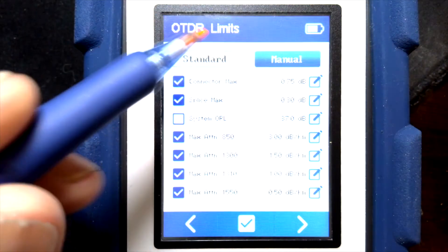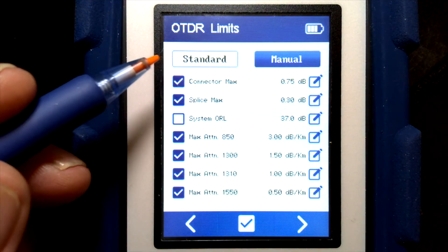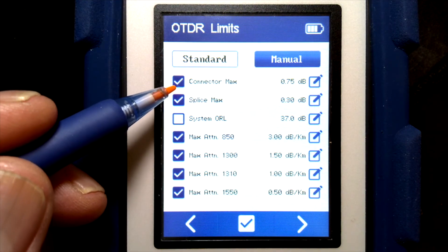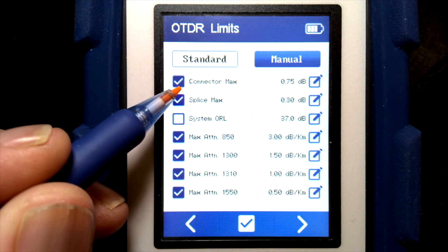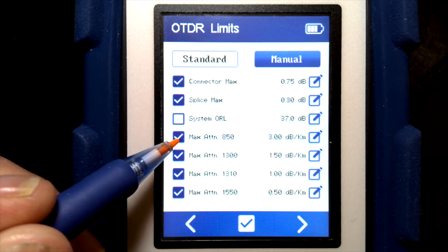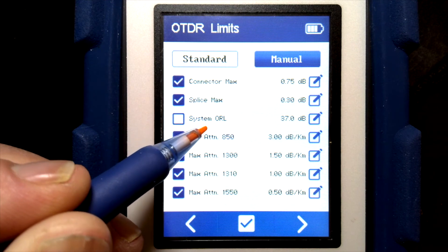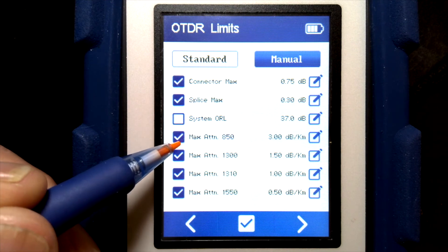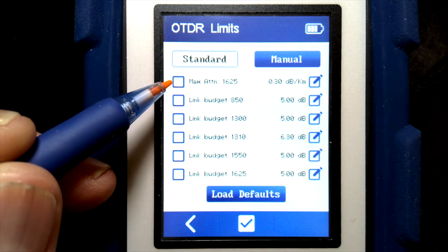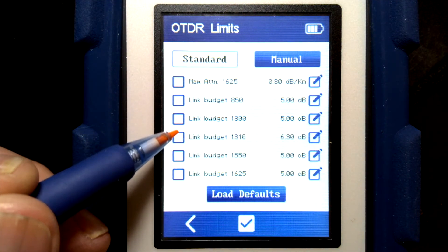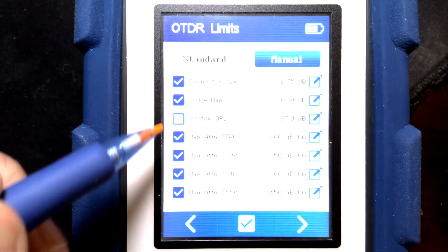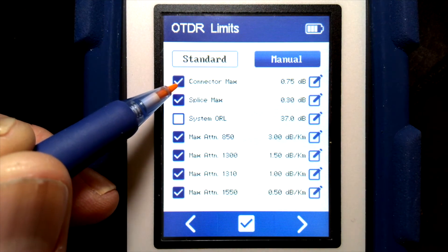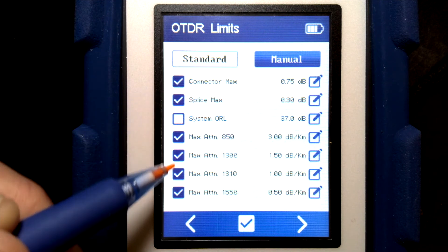If we choose manual, it's just like we saw with the cabling standards, where we can choose the max connector and splice loss, system ORL — which is optical return loss — or the max attenuation coefficient. On the next page, we can also choose the total link loss. You can check or uncheck any of these options, and it will only pass/fail test against the options that are checked.